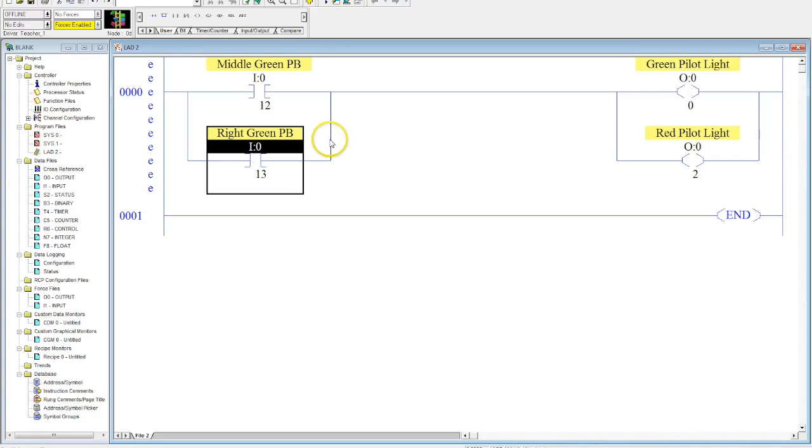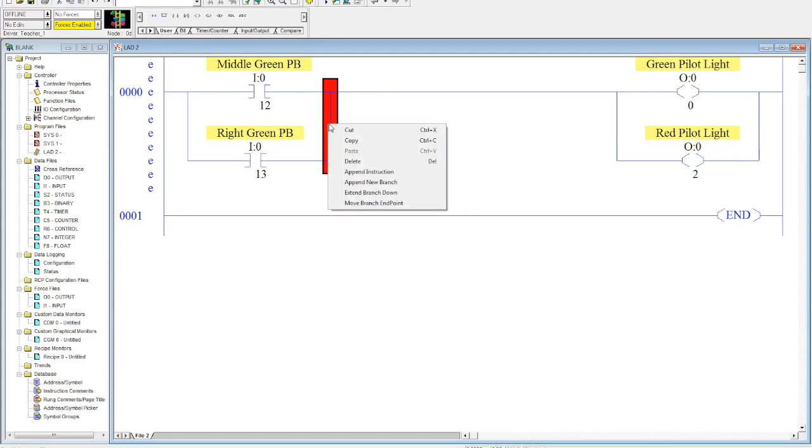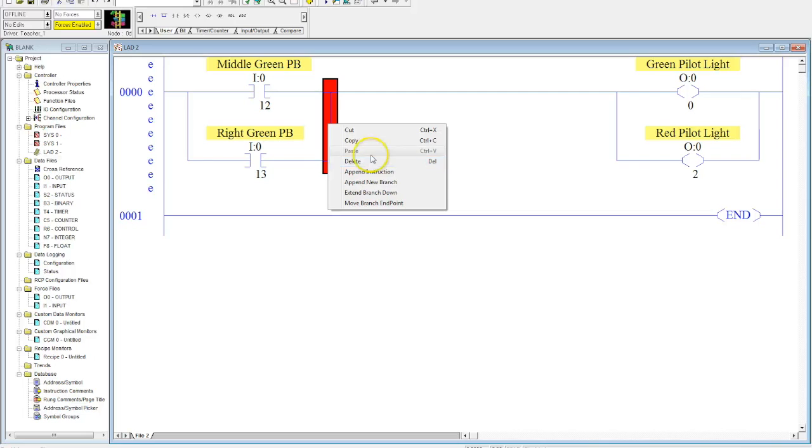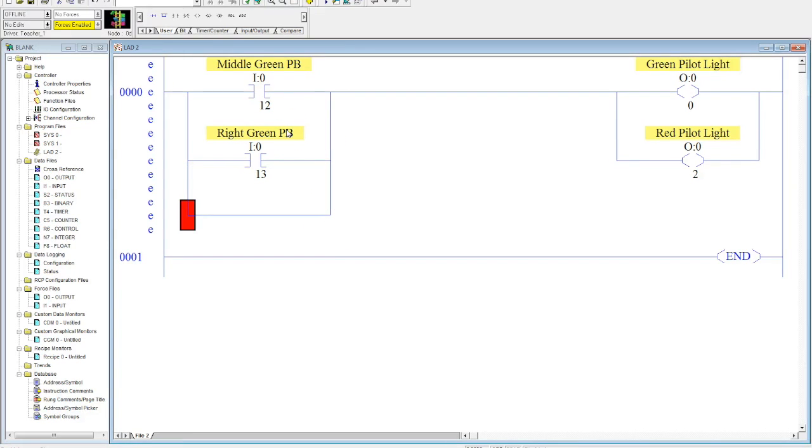They come over here to the right side of your rung branch, and you right click. An option menu comes up, gives you a certain number of things, cut, copy, delete. But what we want to do here is we want to extend branch down. And when I do that, I get a very smooth-looking, very nice-looking three-rung parallel branch.